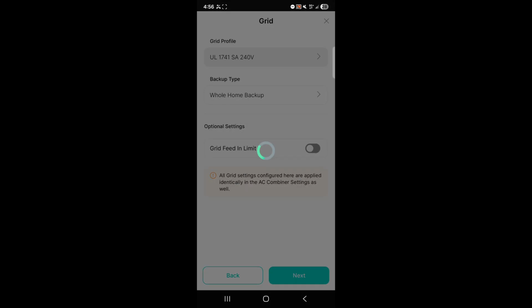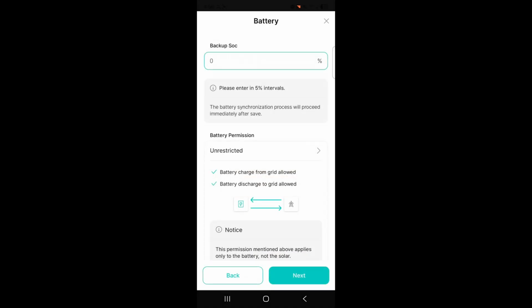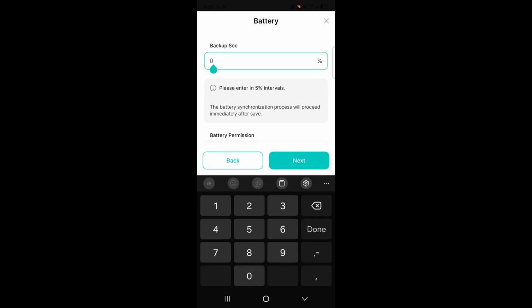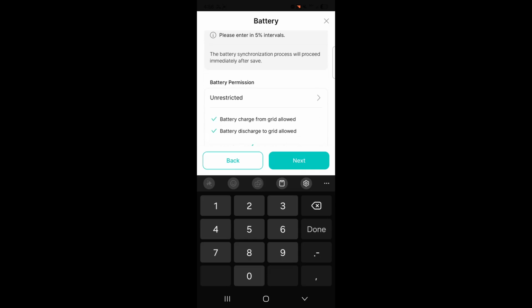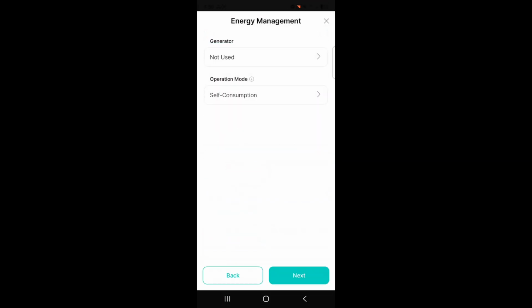Battery SOC. From here you can set a minimum state of charge, or SOC, for the ESS. This will reserve some of the battery capacity for a backup event. Battery operation modes. Unrestricted is the default setting. This will allow battery power to charge from the grid, and battery will export power to the grid. Energy management. Select the presence of a generator. Select the operation mode. Self-consumption is the default, and it prioritizes battery power for home loads.